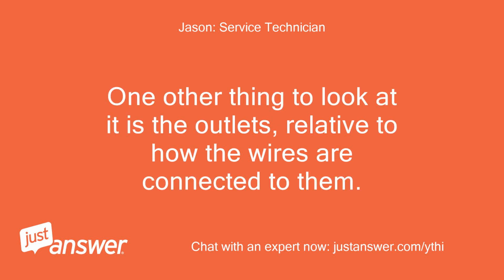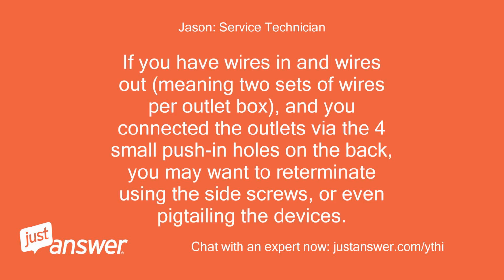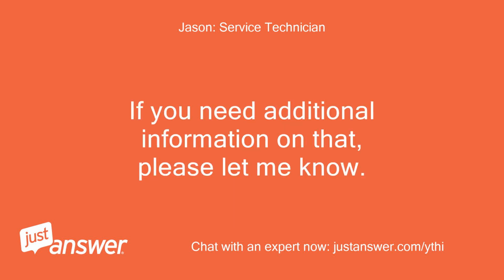One other thing to look at is the outlets, relative to how the wires are connected to them. If you have wires in and wires out, meaning 2 sets of wires per outlet box, and you connected the outlets via the 4 small push-in holes on the back, you may want to re-terminate using the side screws, or even pigtailing the devices. If you need additional information on that, please let me know.